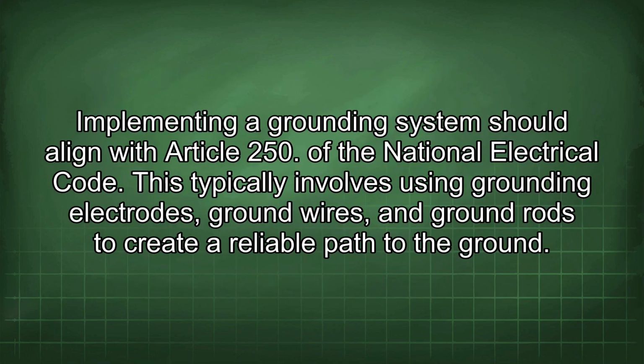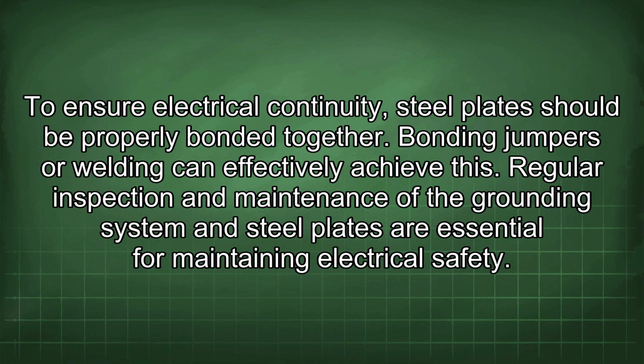Implementing a grounding system should align with Article 250 of the National Electrical Code. This typically involves using grounding electrodes, ground wires, and ground rods to create a reliable path to the ground. To ensure electrical continuity, steel plates should be properly bonded together. Bonding jumpers or welding can effectively achieve this.